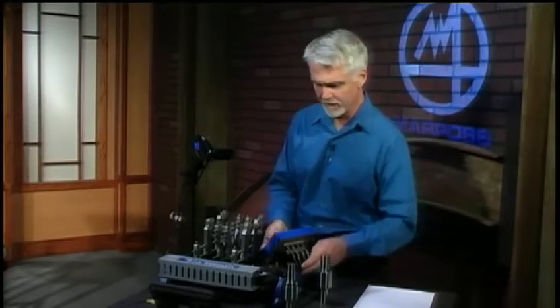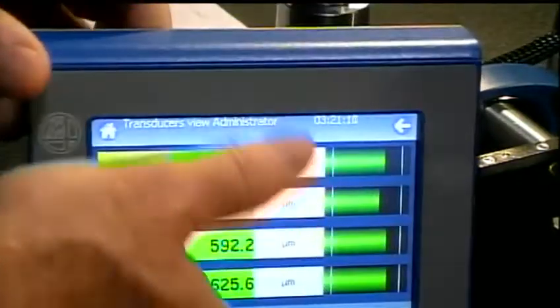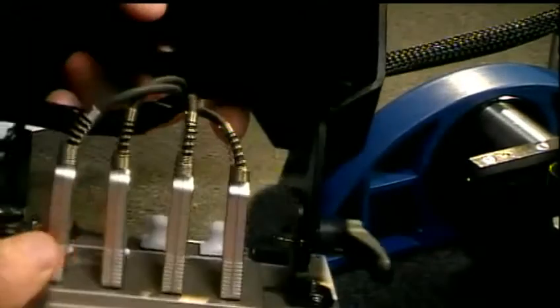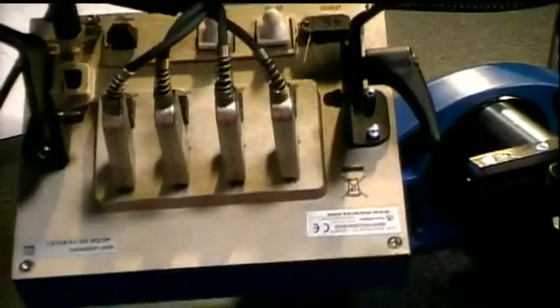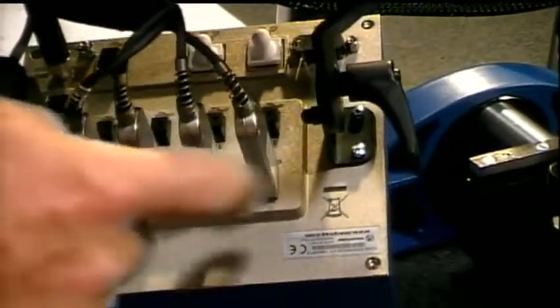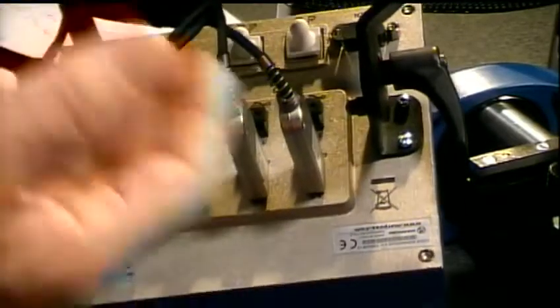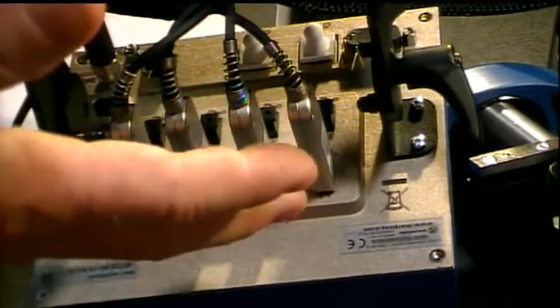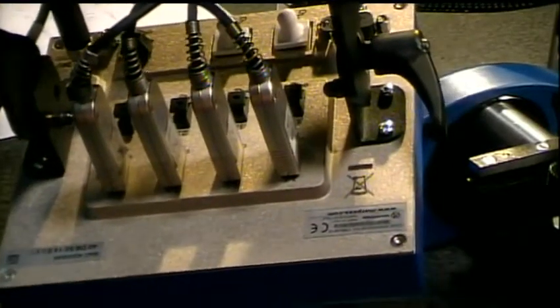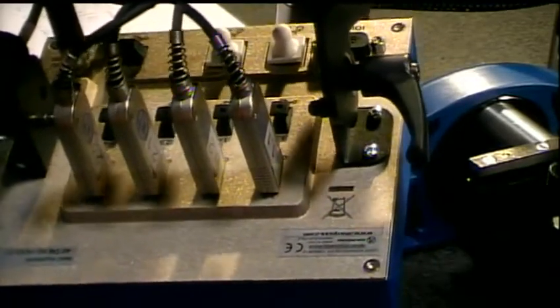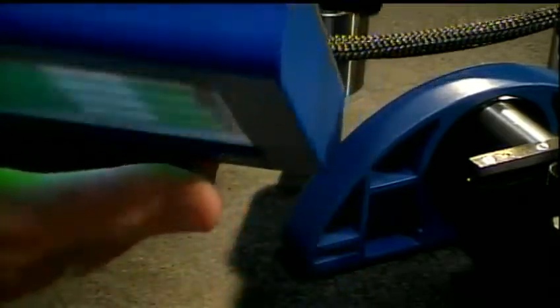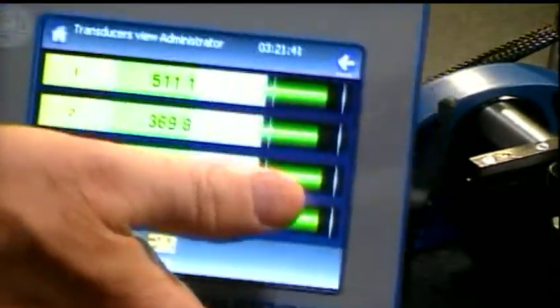Let's take a look at the back of the Nemo first. This is called the Nemo8—it's an 8 USB input gauge calibration, gauge computer. You can see we've got 4 inputs already used up, and there are another 4 inputs down here on the bottom, so 8 USB inputs total. There's also a couple of Ethernet connectors so you can send your data to a computer on your LAN, and an RS-232 connector for outputting data serially, maybe to a laptop or another computer.